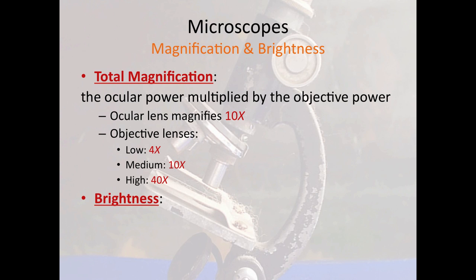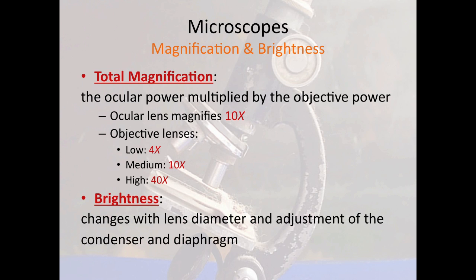You will notice on the microscopes in lab that there is a fourth objective lens. We won't be using those — that's an oil immersion lens. If you see your lab partner trying to look at something through that fourth objective lens, tell them they are not qualified to be using that expensive piece of equipment. Regarding brightness: the brightness of the image changes both with your choice of objective lens and by adjusting the condenser and the diaphragm. Many students who are convinced they've mastered microscopy say they can't find anything, because they either have no light or too much light shining through the lenses. Figure out how to adjust the light and you'll be two steps ahead.